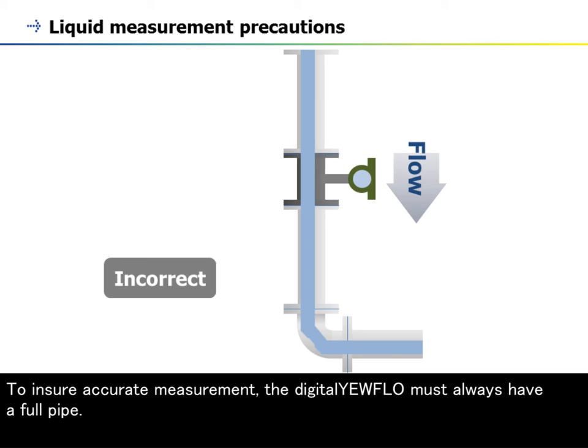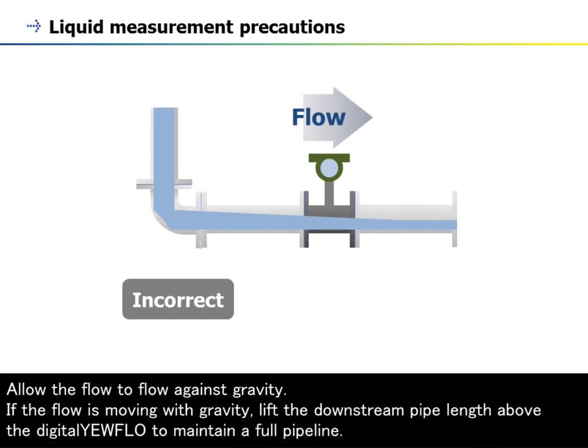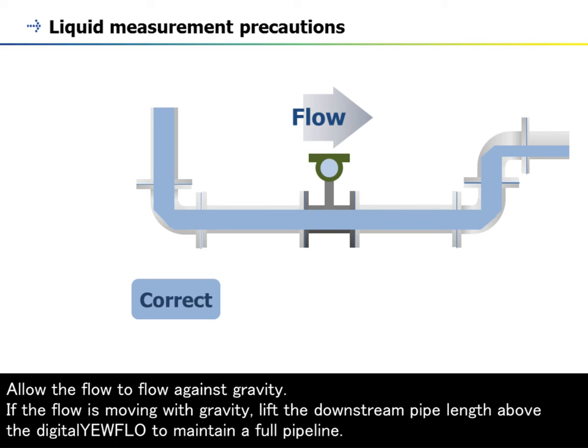To ensure accurate measurement, the digitalYEWFLO must always have a full pipe. Allow the flow to flow against gravity. If the flow is moving with gravity, lift the downstream pipe length above the digitalYEWFLO to maintain a full pipeline.